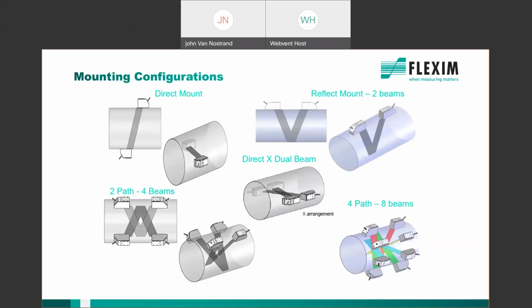So the question often comes up about straight runs. How much straight run do we need? Now, there are a lot of concerns out there with old pipes where you don't have a lot of straight run. So we recommend that you have 10 diameters upstream and 5 downstream if possible. But if that's not attainable, there's something we can do to shorten a recommended distance. And we offer something called a profile correction, which is a correction factor based on empirical data that we've collected for many years, testing many applications. So we can actually take a radius of the bends ahead of the meter, the distance, and so on, and we can program that into the meter and put in the correction factor.